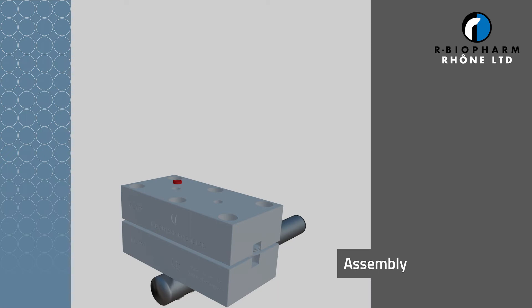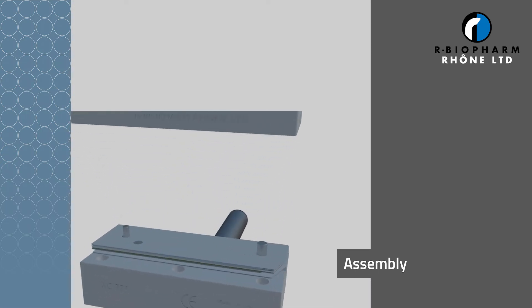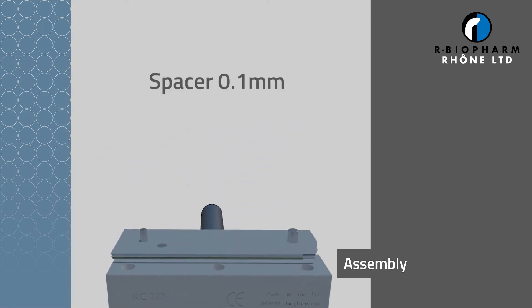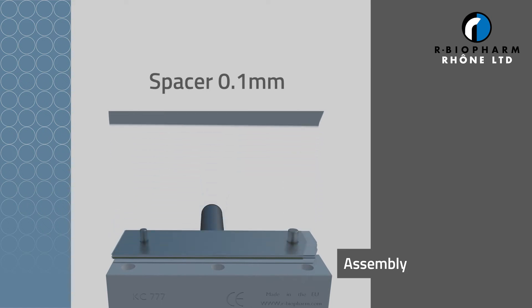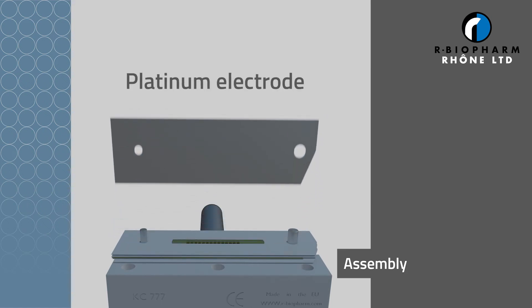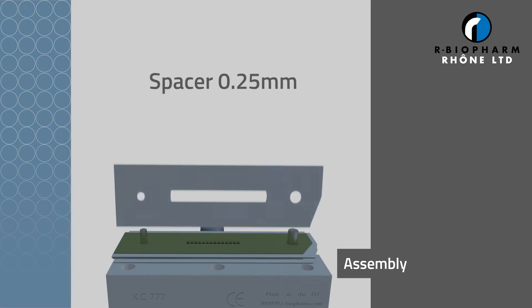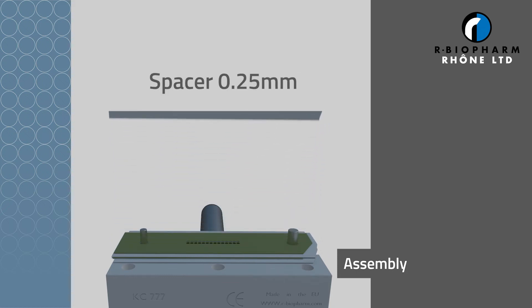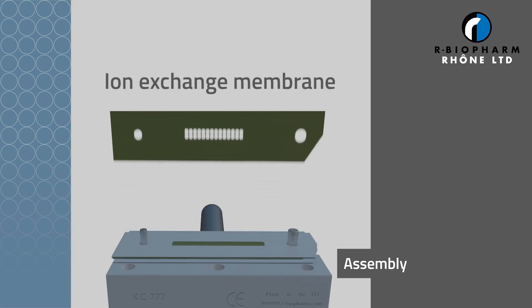The COBRA cell contains a platinum working electrode and a stainless steel auxiliary electrode, which are separated by a membrane and various spacers. These are sandwiched between a rigid plastic housing. The cell is fitted between the HPLC column and the detector.